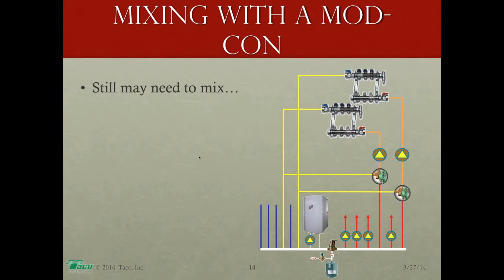We see those 4 circulators down on the red side that are distributing heat to panel radiator zones. Let's say those are at 150 degrees. And then we have our radiant floor heating in between the floor joists and our radiant floor heating in the slab, 2 separate water temperatures. If the radiant floor heating in between the floor joists needs 130 degrees, well, if we use a mixing device of some kind to get down to 130 degrees under design conditions, we'd simply set up, in this case, a 3-way motorized mixing valve like you see here.